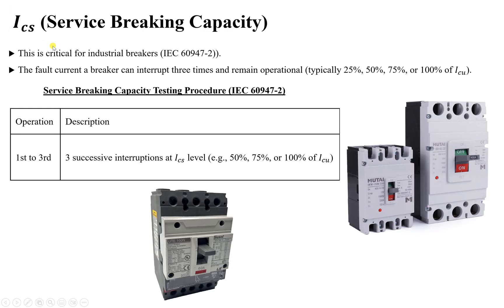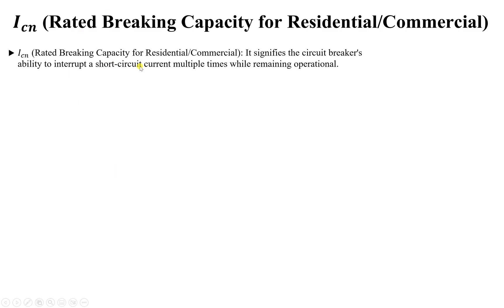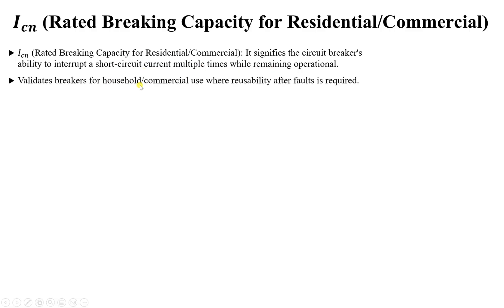The third definition is ICN. Both ICS and ICU are defined under IEC 60947-2 for industrial applications. ICN, however, is defined under a different IEC part related to residential and commercial applications. ICN stands for the Rated Breaking Capacity. It signifies the circuit breaker's ability to interrupt a short circuit current multiple times while remaining operational.